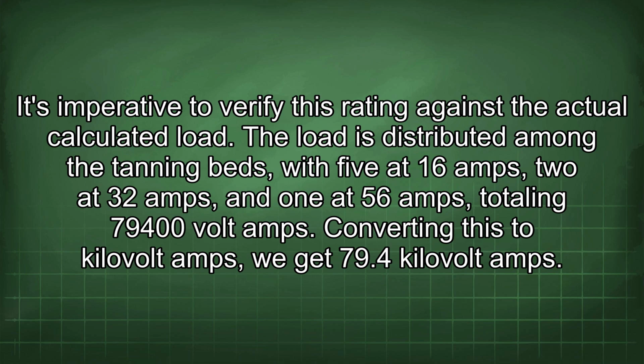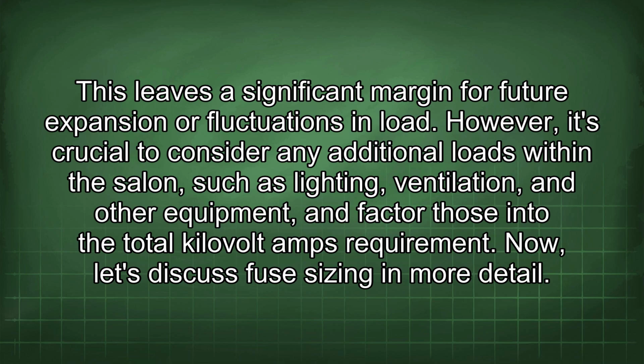The load is distributed among the tanning beds, with 5 at 16 amps, 2 at 32 amps, and 1 at 56 amps, totaling 79,400 volt amps. Converting this to kilovolt amps, we get 79.4 kVA. This leaves a significant margin for future expansion or fluctuations in load. However, it's crucial to consider any additional loads within the salon, such as lighting, ventilation, and other equipment, and factor those into the total kVA requirement.